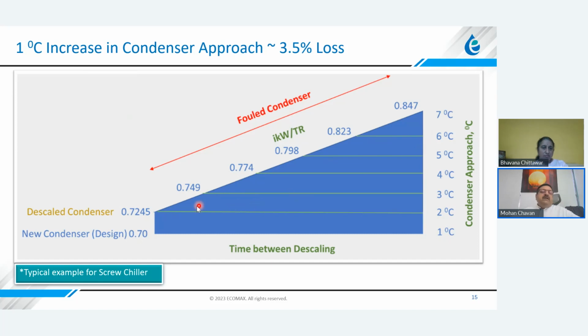Now you can imagine the energy loss that is taking place from this point to this point, okay? And this is the time here. What we are losing is the area under this curve. If we are able to avoid this triangle and keep this flat like this, you will save all this energy. Now this is possible with technology. This is an online condenser tube cleaning system. It's possible to maintain an approach between 1 to 2 throughout the year by using a ball type ATCS.